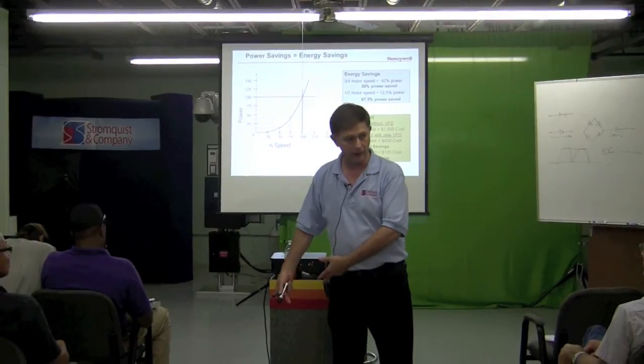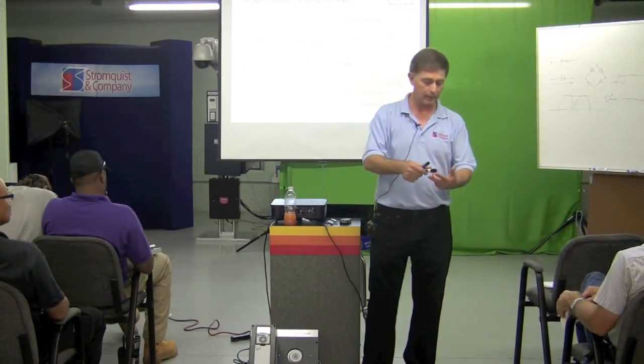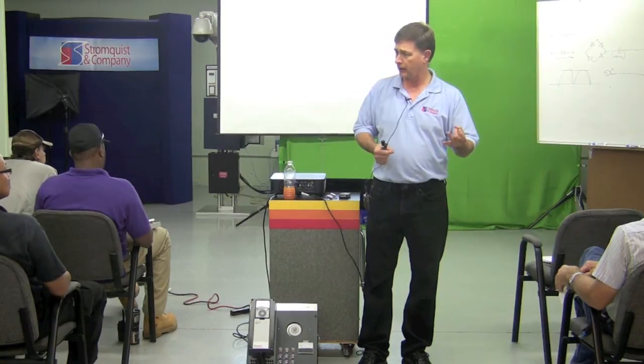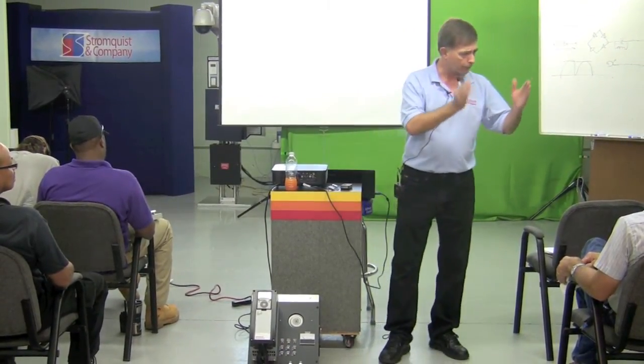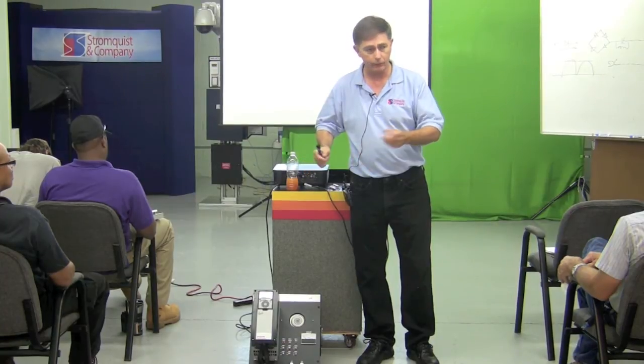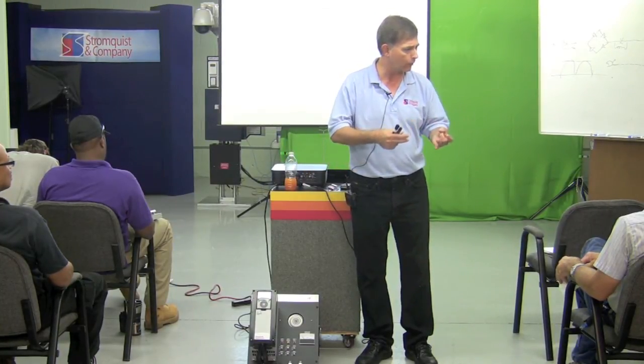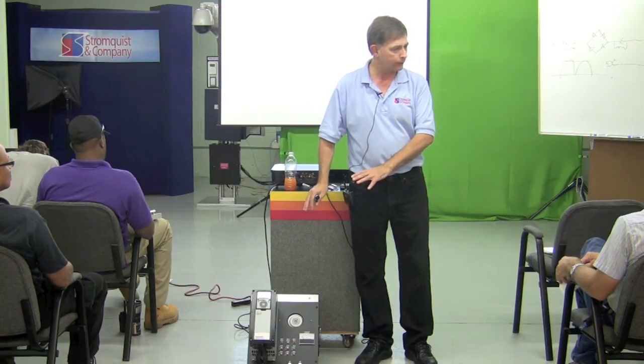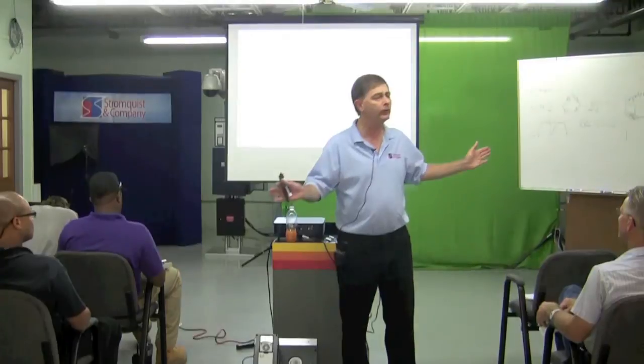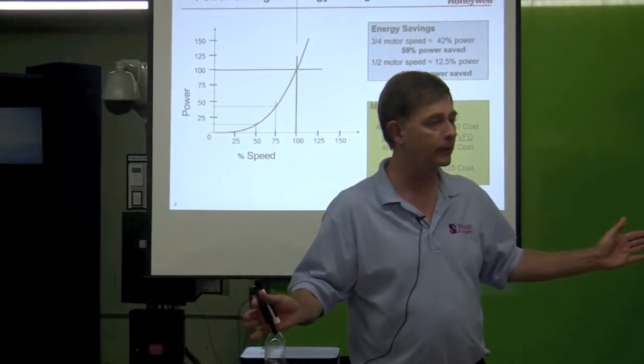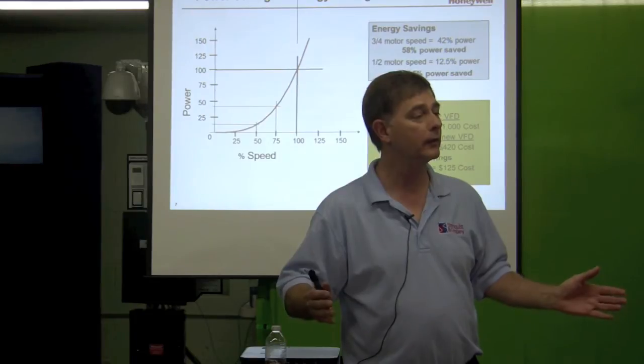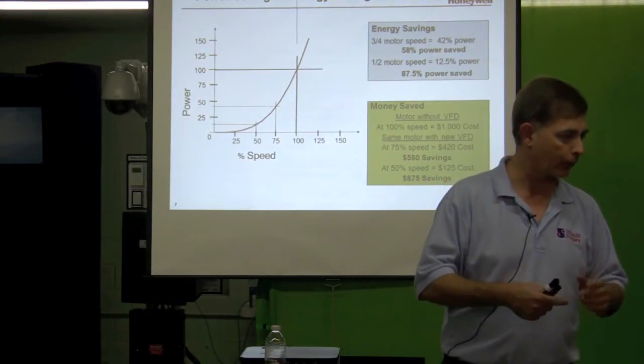I'll show you the setup on the Honeywell, and it basically asks you, it throws most of the startup into one of two categories. Is it a pump or is it a fan? If you look at pumps, most of the parameters with pumps are similar. Most of the parameters for a fan are similar. So if you tell it, if it's a pump or a fan, give it a little bit more information, it knows how to control 9 times out of 10 applications. Then there's some applications, if you have a huge fan, maybe 30 seconds, that's the default for a fan on the ramp up time. Maybe that's a little bit quick. Maybe you want to slow it down a little bit. I'll show you how to change that parameter. It's real easy.